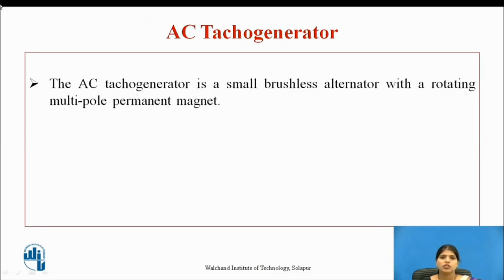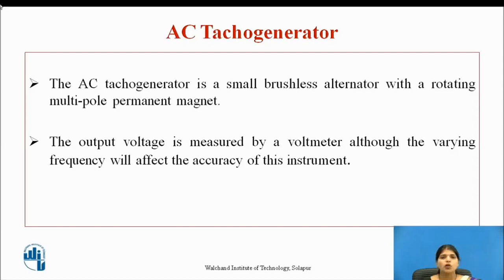The AC tachogenerator is a small brushless alternator with a rotating multipole permanent magnet. In the AC tachogenerator, the armature is provided with an AC winding, either single phase or three phase windings. The output voltage is measured by a voltmeter, although the varying frequency will affect the accuracy of this instrument.